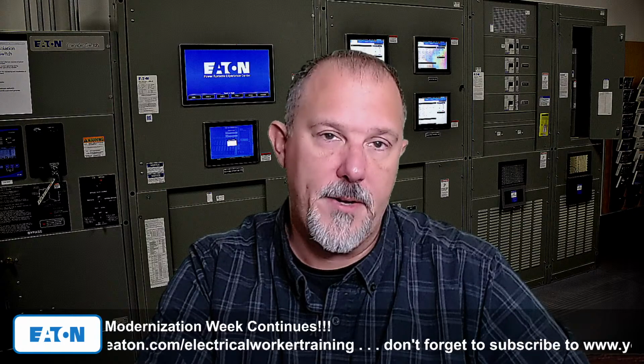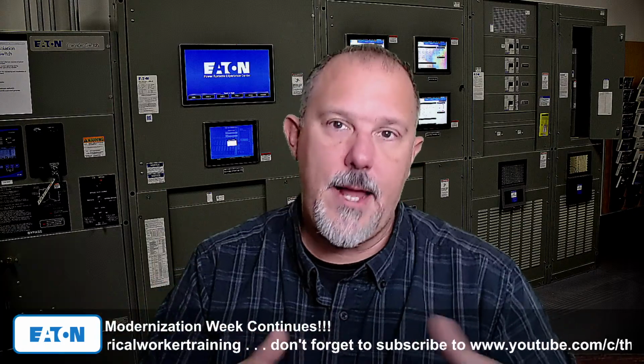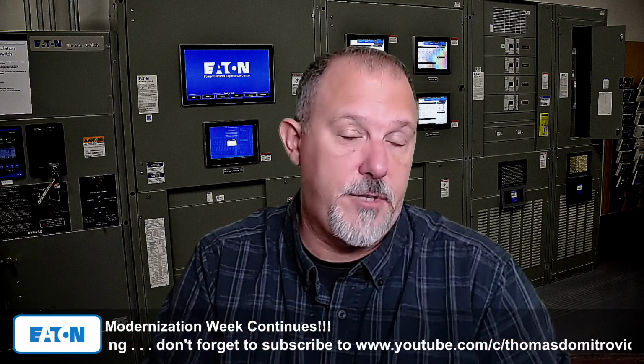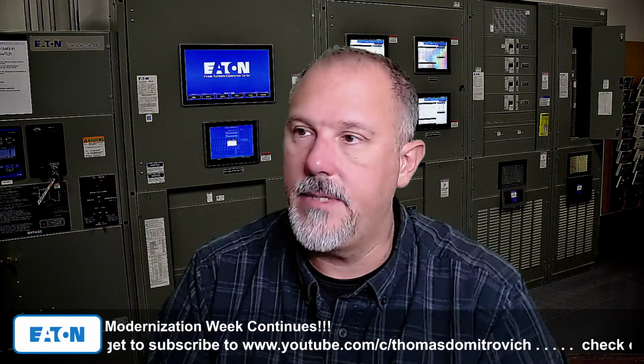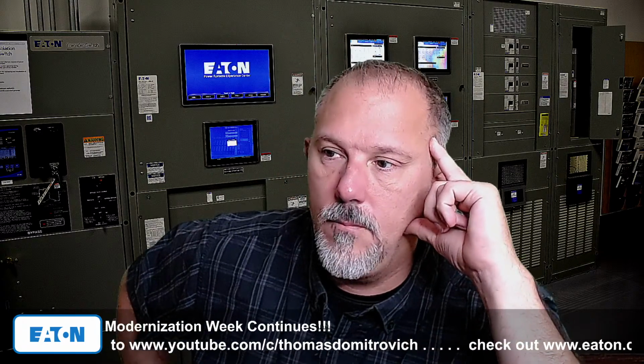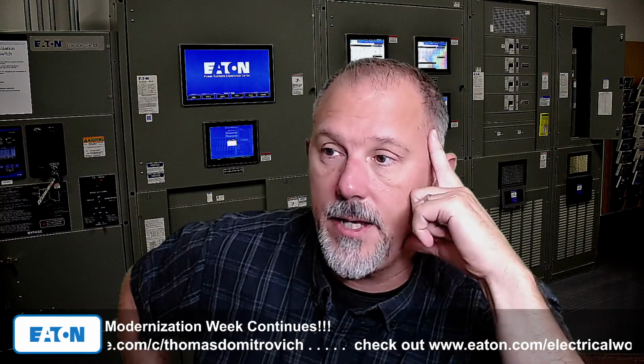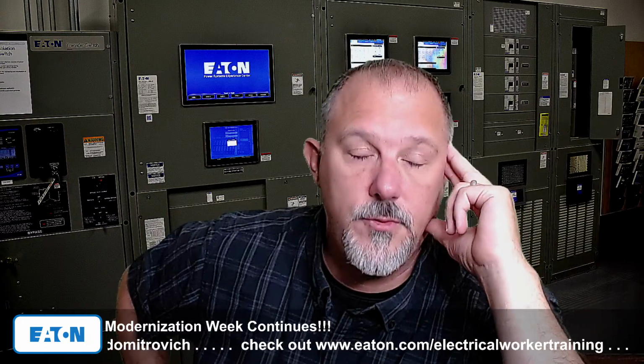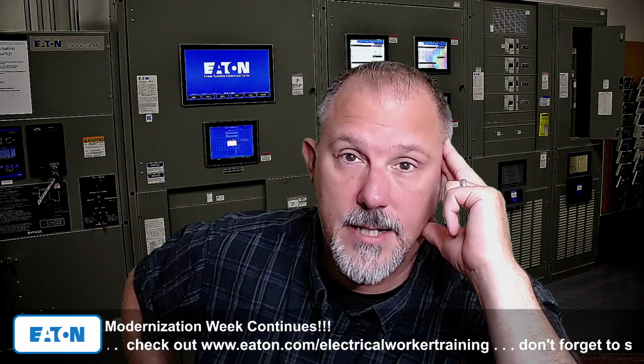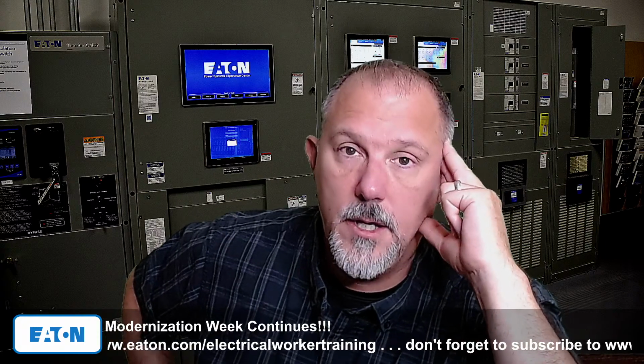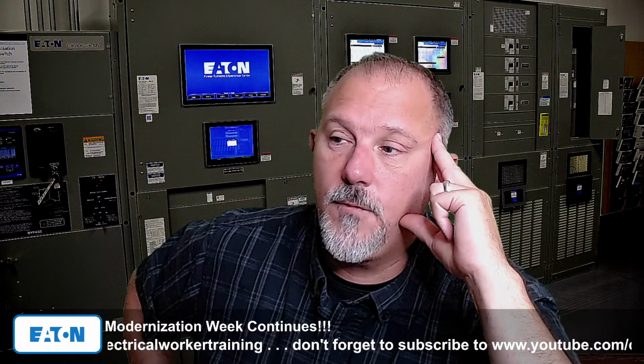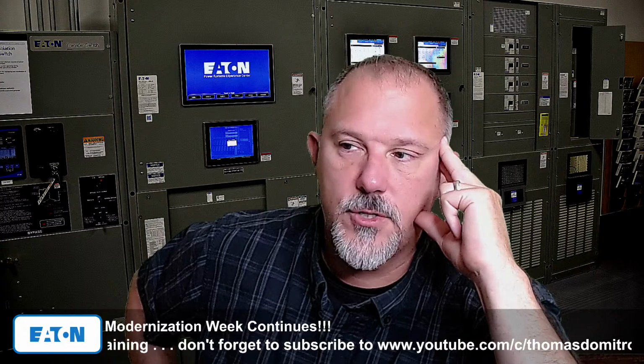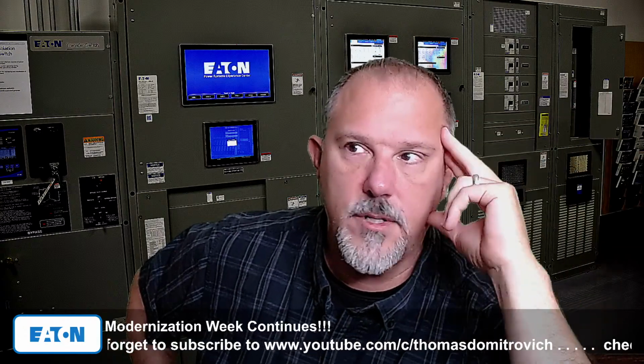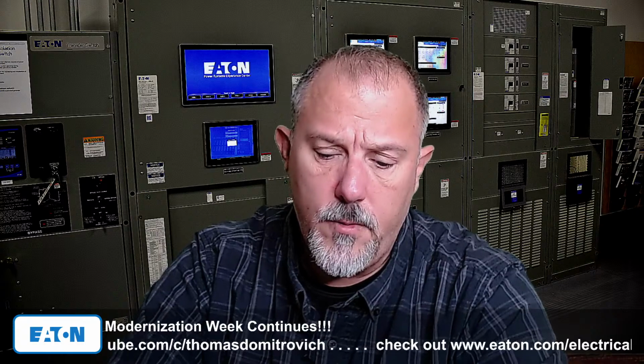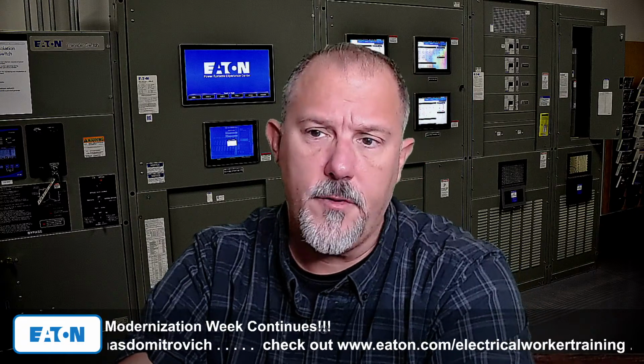And if there's a wiring problem, if you lose that bond and now that case is energized, current's going to flow as soon as you touch it, and we've already seen death associated with that. So we don't recommend, I would never say, look, don't put GFCI on there. I mean, Panel 2 just approved a tentative interim amendment for some AC units, not all. And I'm not sure, I think it's gone through and it's probably out there on the website. But are there some units that cause earth leakage and use that?